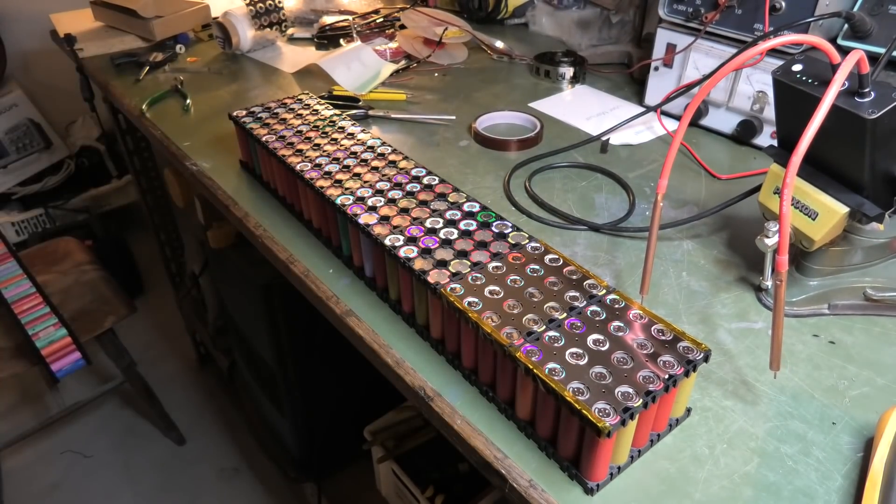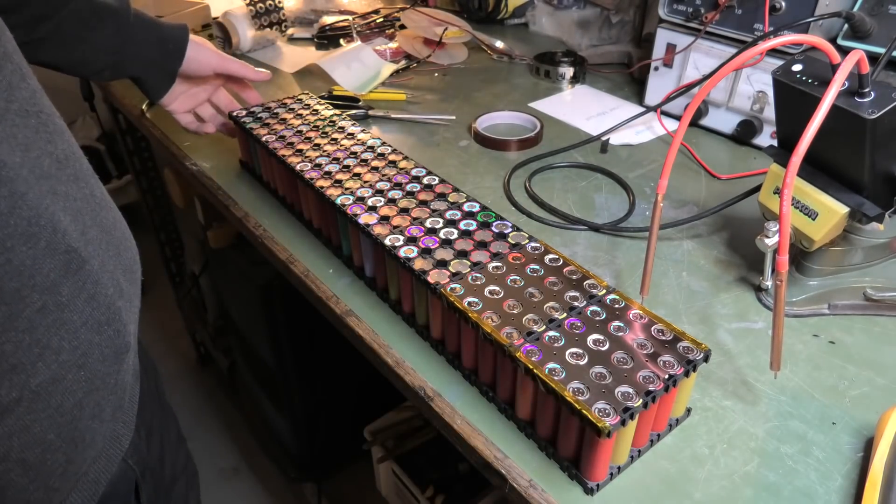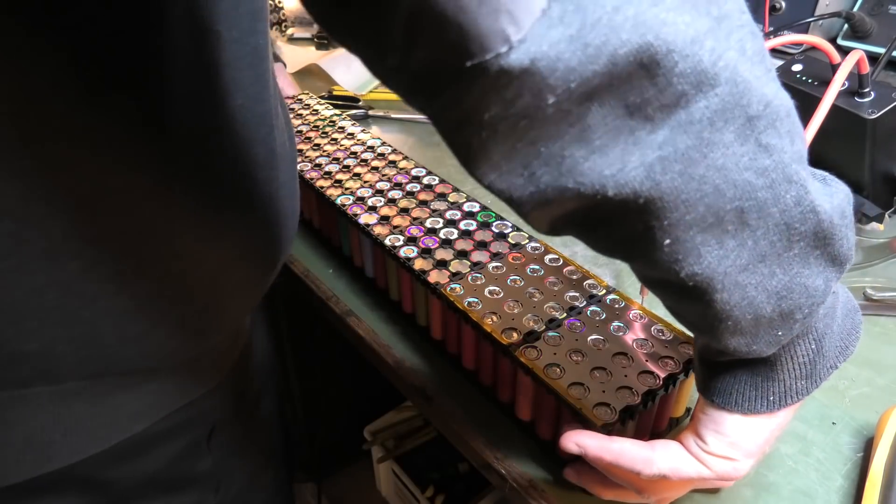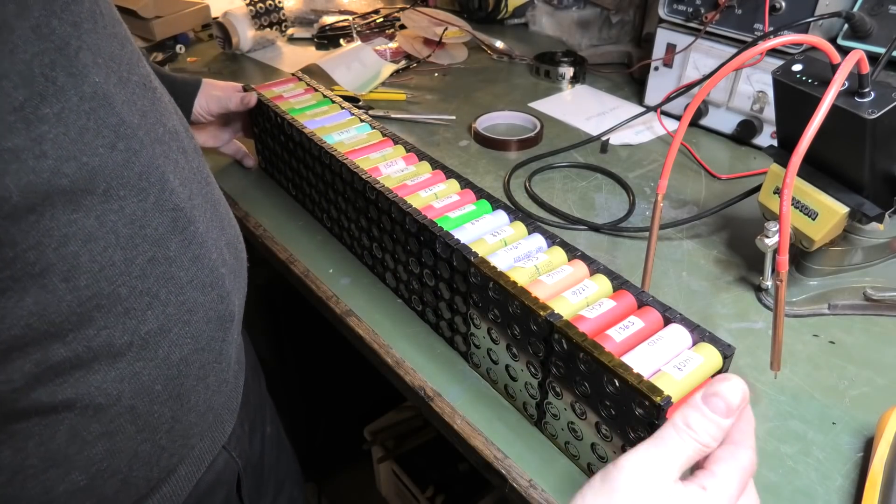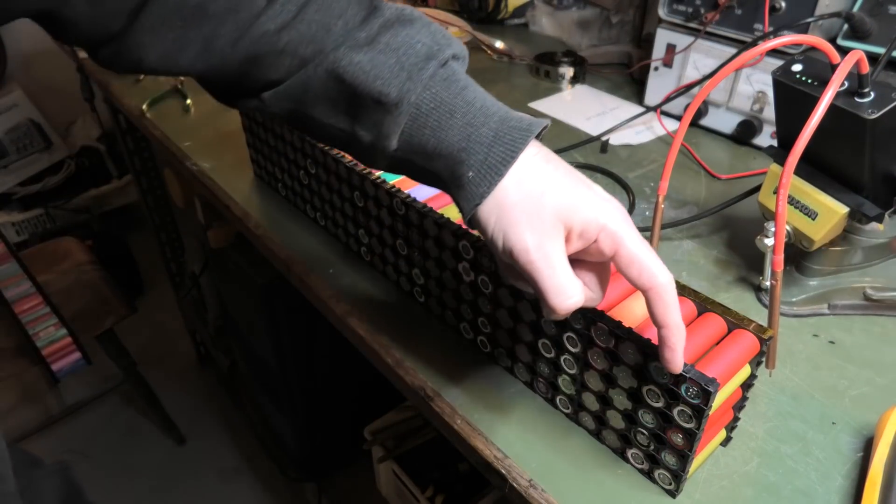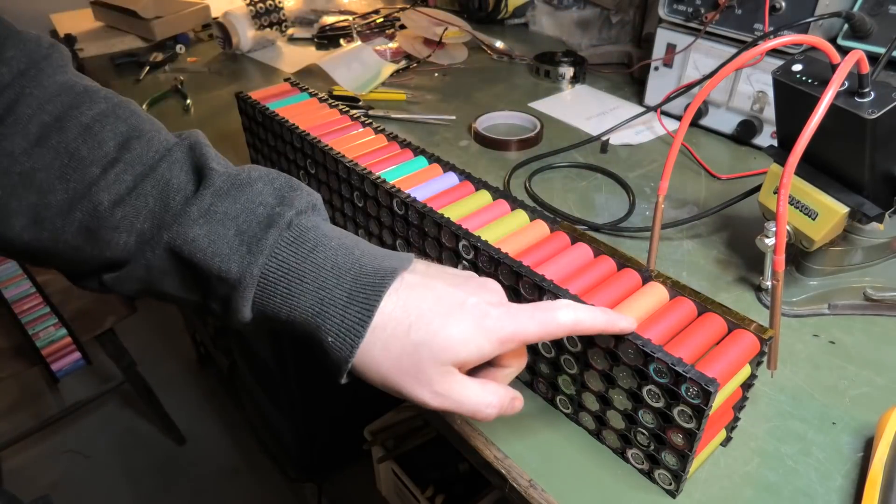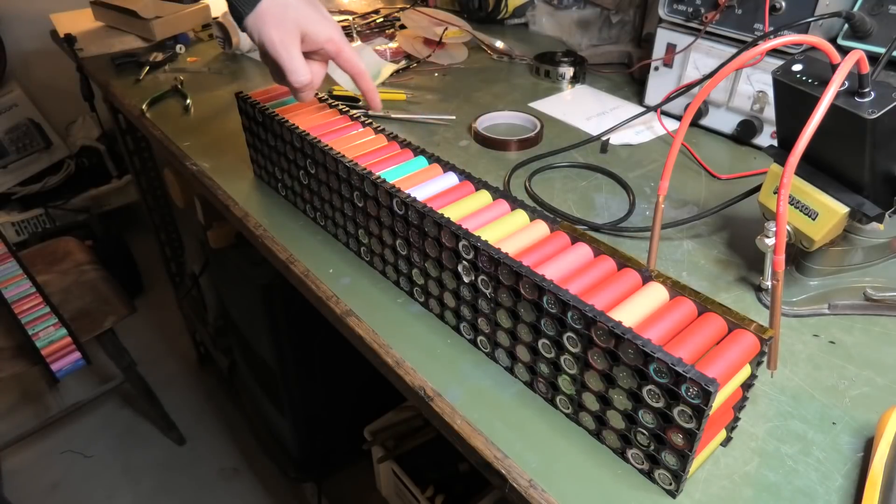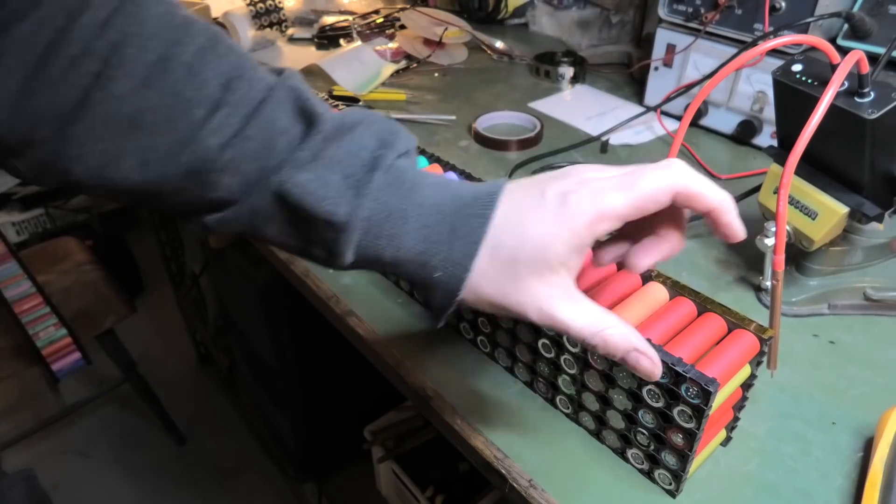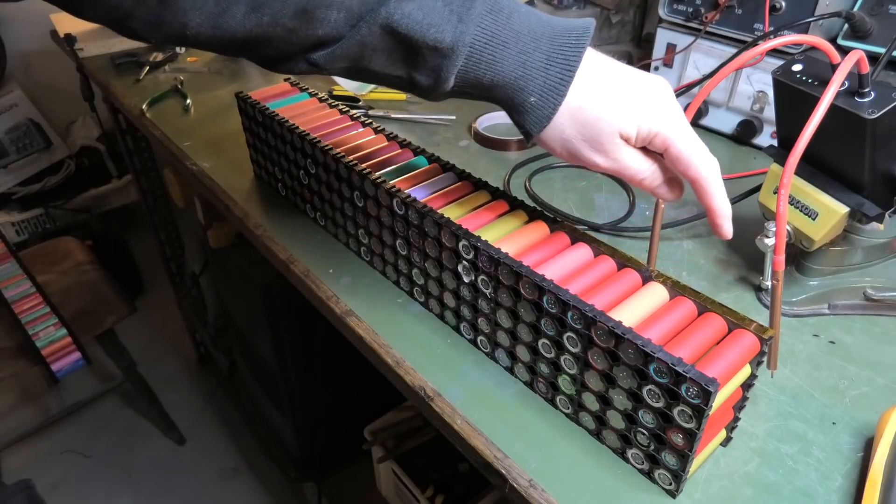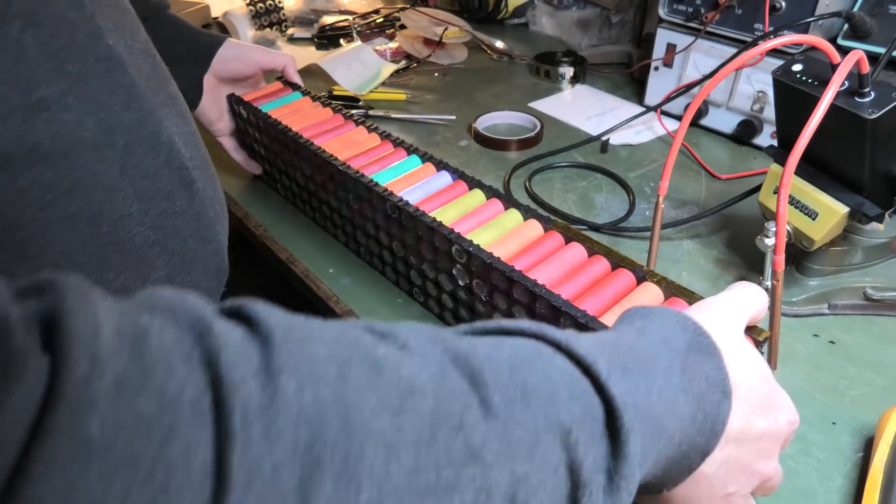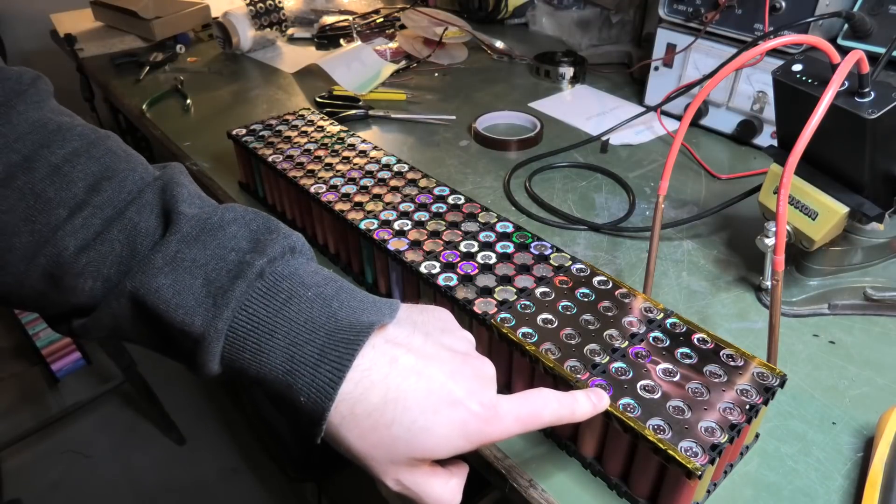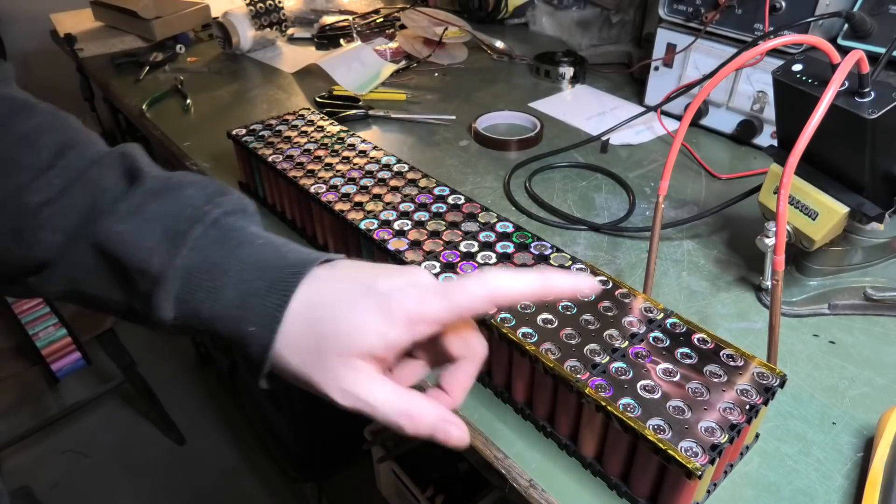There is a meaning to the madness here, because everything here needs to go in series. So that's actually the wrong side we're looking at there. So here is the most positive. Then it goes around the back and then it connects this way. And over here it's going to connect. So it's going to snake all the way down here, 14 batteries, 14 sets of batteries. Each of them contains 10, is going to be connected in series with the next 10 batteries and the next and the next. So that's why this is how it is. This is snaking it through, connecting the pluses here with the minuses here and so on.